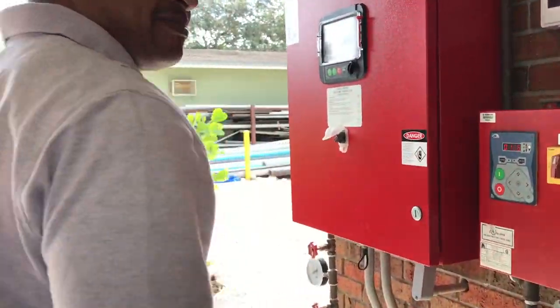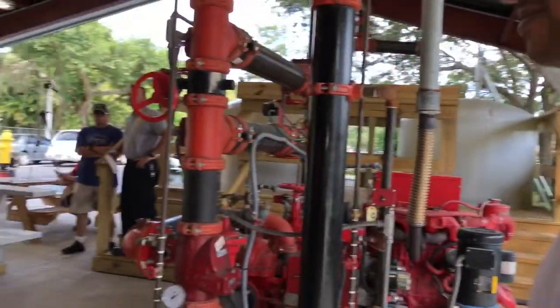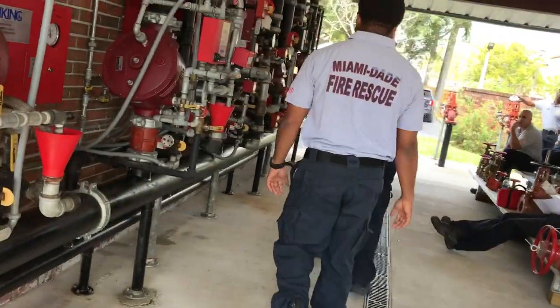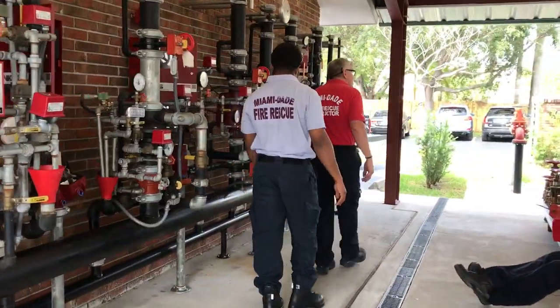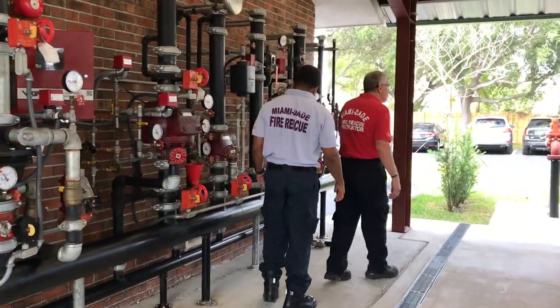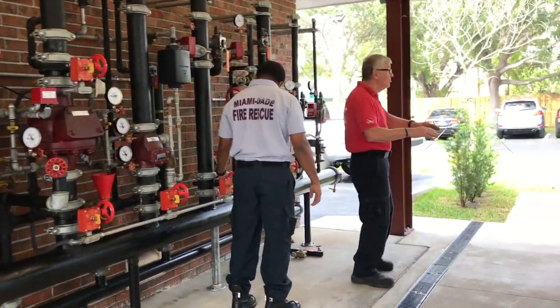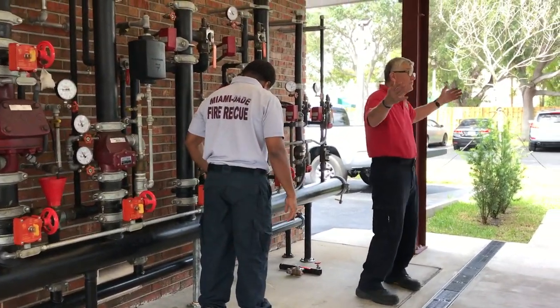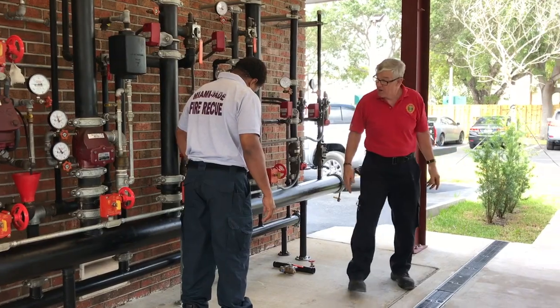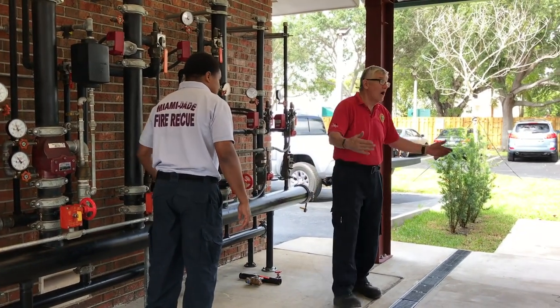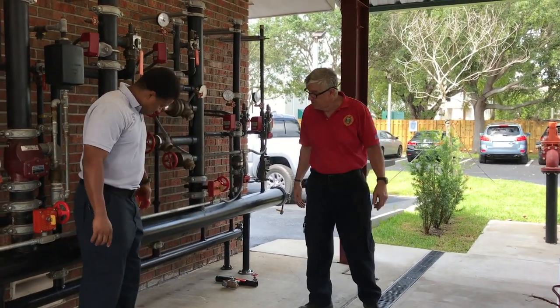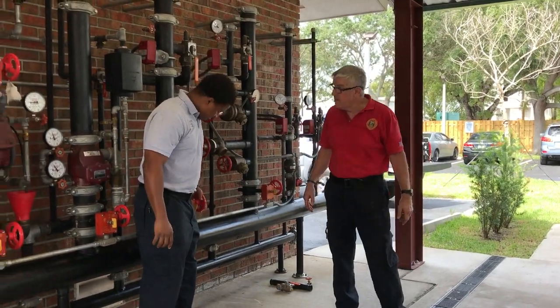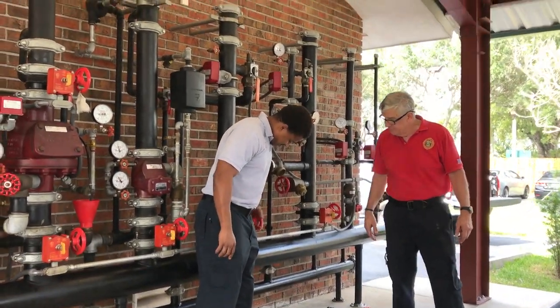I know we're getting ahead of ourselves. Mark, we'll go ahead and we'll turn the riser on the rest of the way. Okay, do you see why we don't want to fill that piping with the fire pump? Because you go from zero pressure to as much as 250, you never know what kind of pressure. But we know water hammer is not a firefighter's friend. Mark, we'll put it back on all the way. All right.